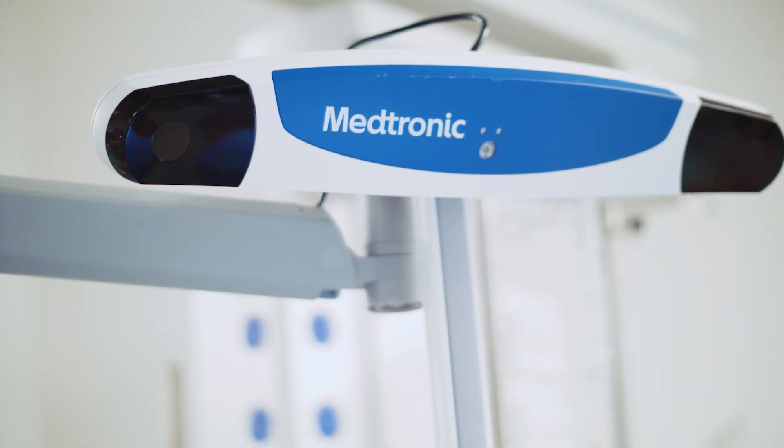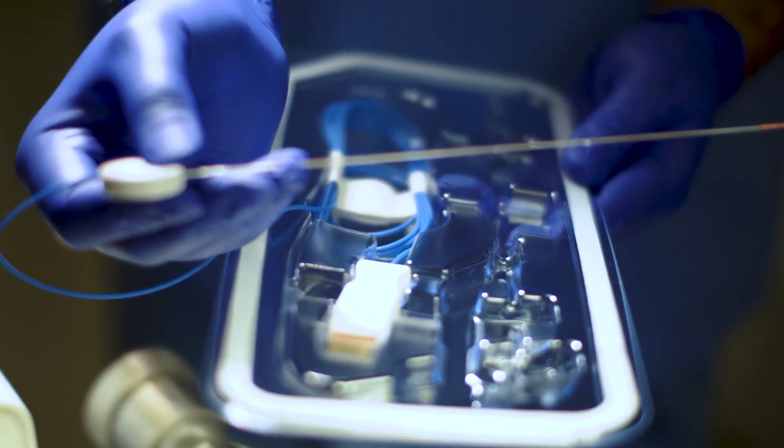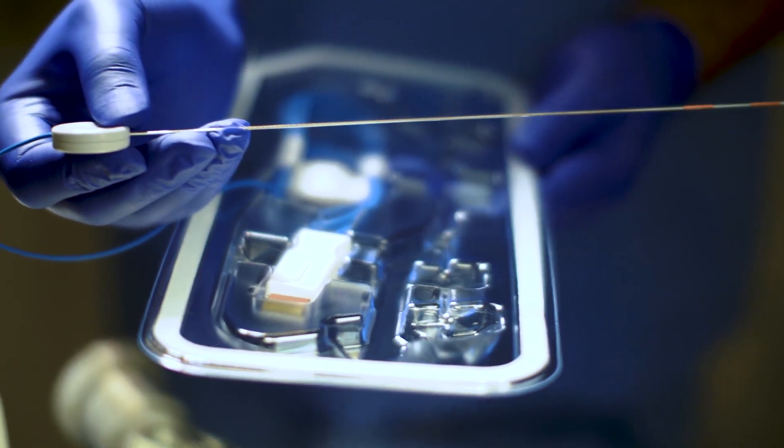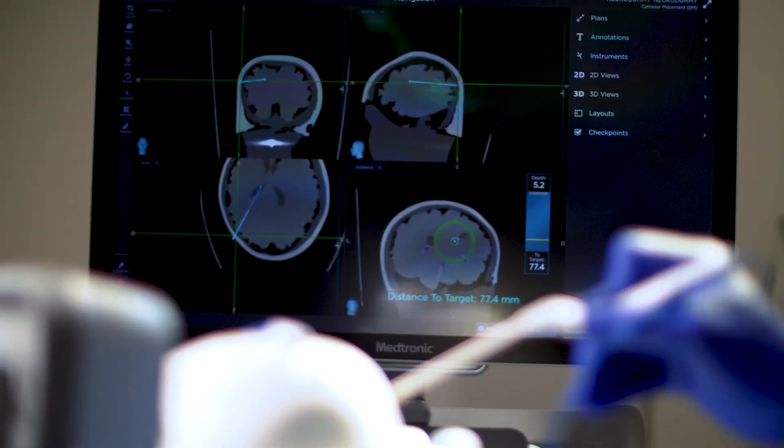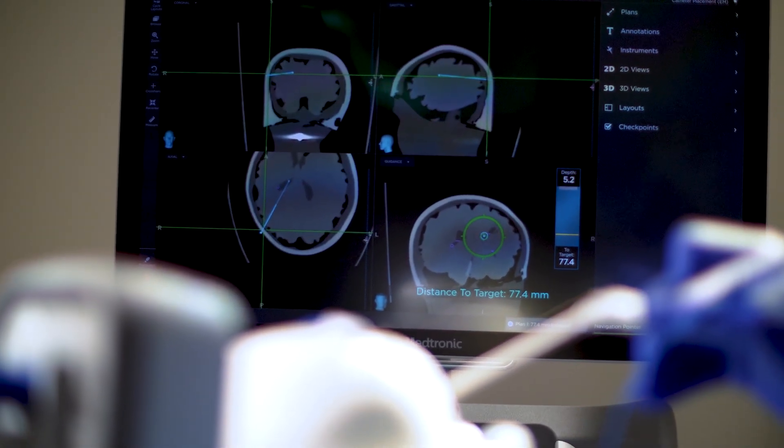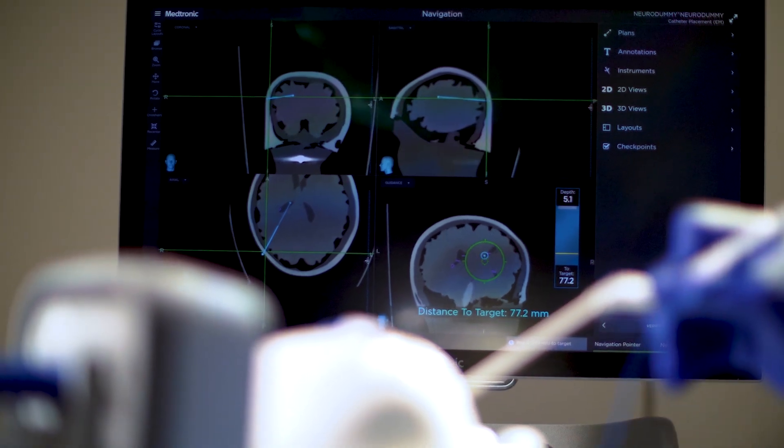This is a Medtronic StealthStation S8. It's a combination of hardware and software that uses special trackable instruments such as this pointer and this stylet. To be able to guide the neurosurgeon, the system tracks the position of these instruments in relation to the surgical anatomy and sends that information to the software, which then displays the instrument's position on either the CT or MRI scan of that patient.